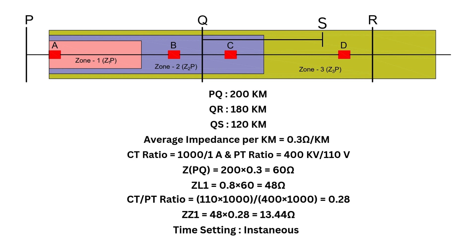This is because transmission lines are not perfectly balanced and there may be slight errors in the CTs and PTs. Setting zone 1 to exactly 100% could result in incorrect tripping for faults just beyond the protected line. By limiting it to 80%, we avoid such unnecessary trips.